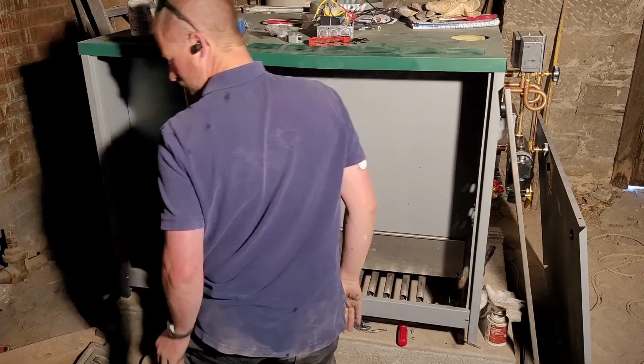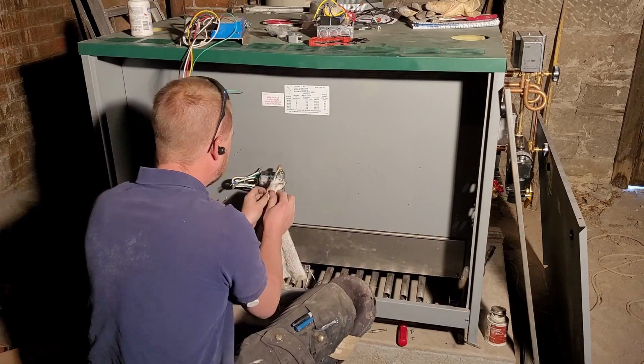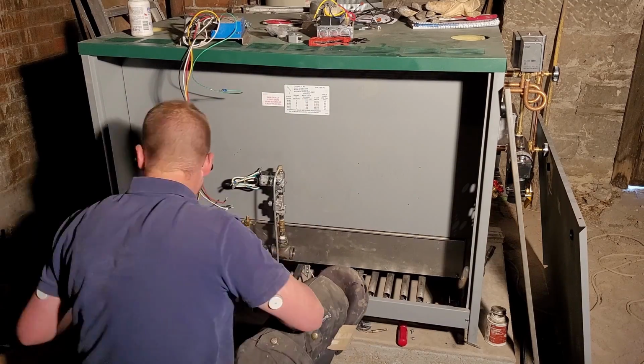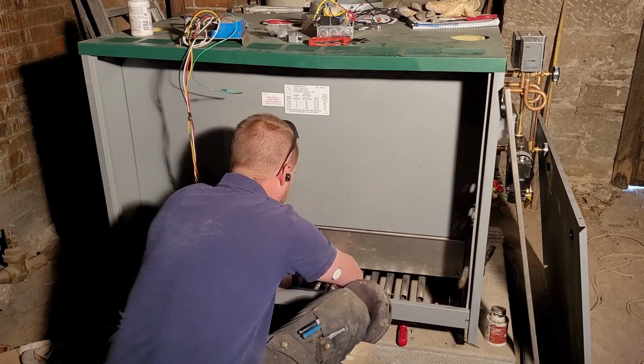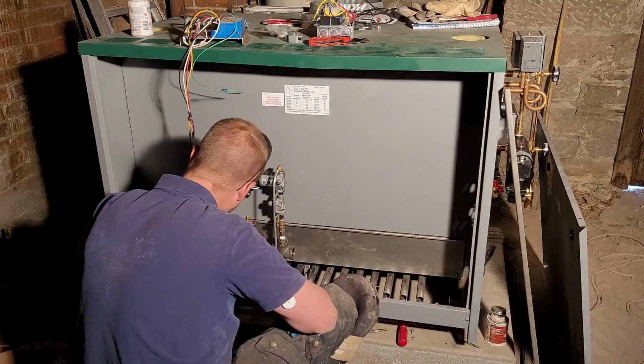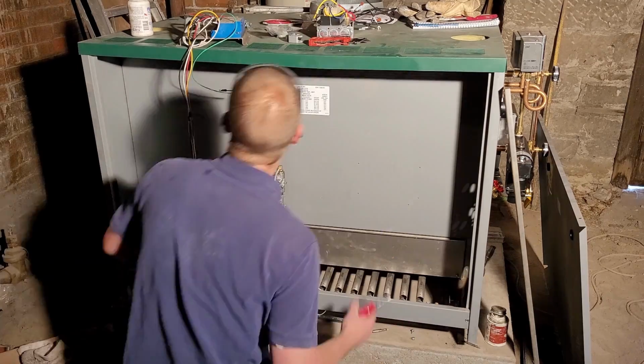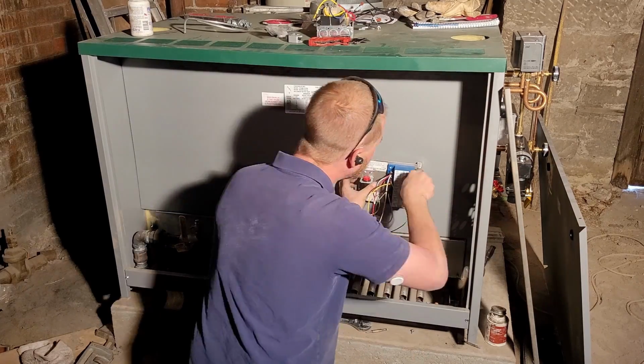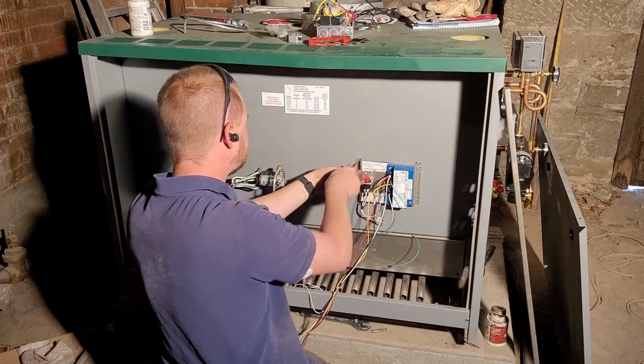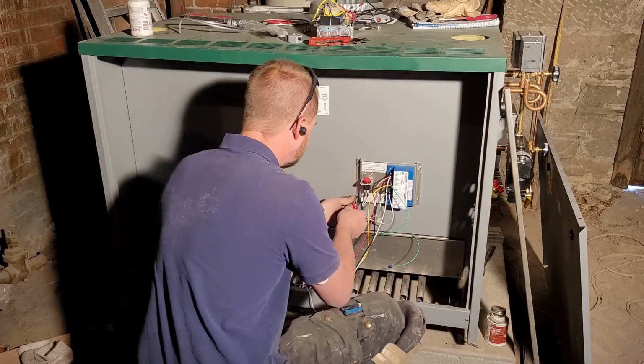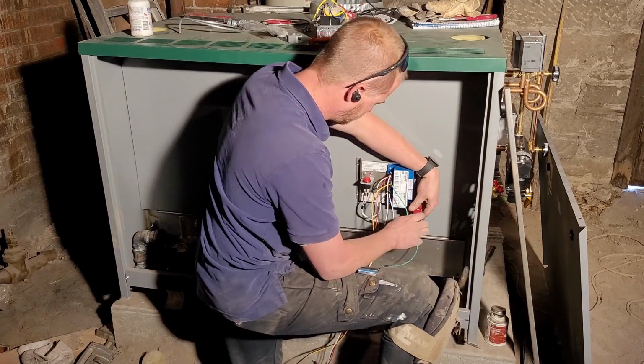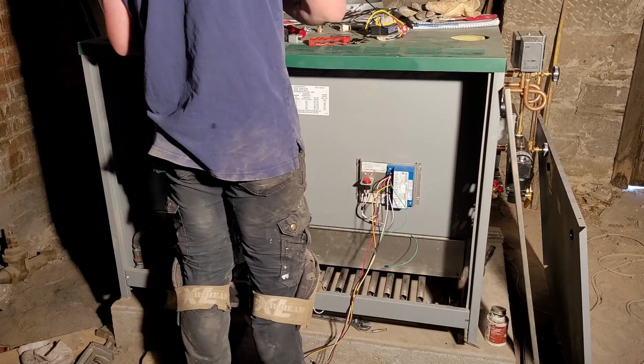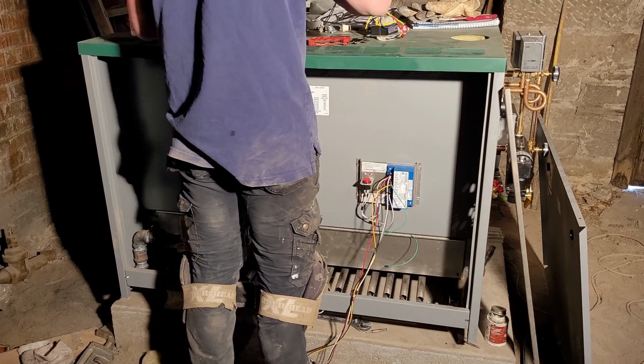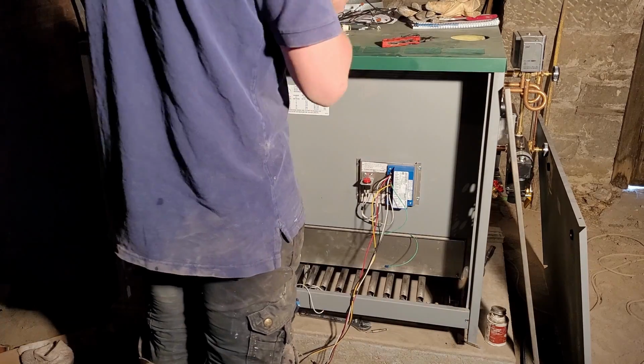There's lots of different mechanisms for how that actually works, but that's the main thing to take away from it. Now, these work very well. They're very reliable. They do last a long time. They were the standard for many, many years. But they have one slight issue, in that if the thermocouple is hot, it will not stop supplying voltage for about 30 seconds if the pilot flame goes out, because they're still hot and they have to cool off before that voltage drops off.